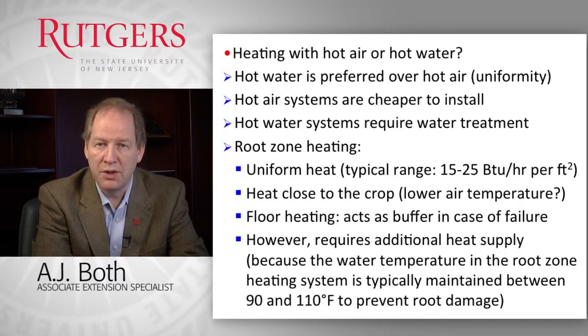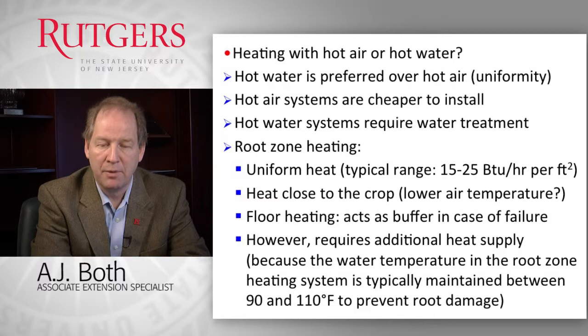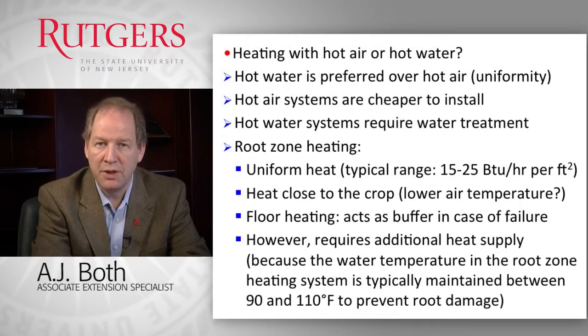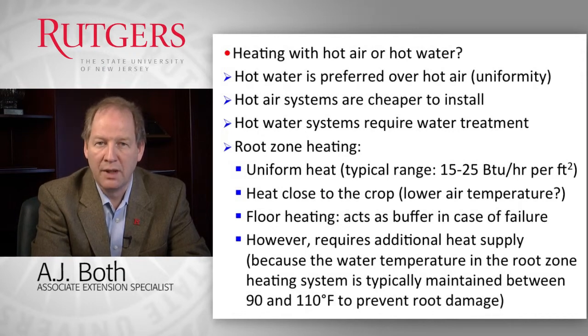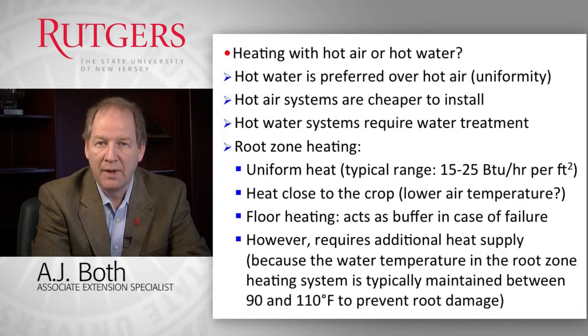If you have a root zone heating system — either pipes embedded in the floor or pipes directly on the bench — that is probably the best system for distributing heat uniformly. However, we can only provide so much heat because plants are grown on the floor or bench, and if temperatures get too high, plants will be negatively affected. So a root zone system provides a base load of heating, and additional capacity must come from overhead pipes or unit heaters.